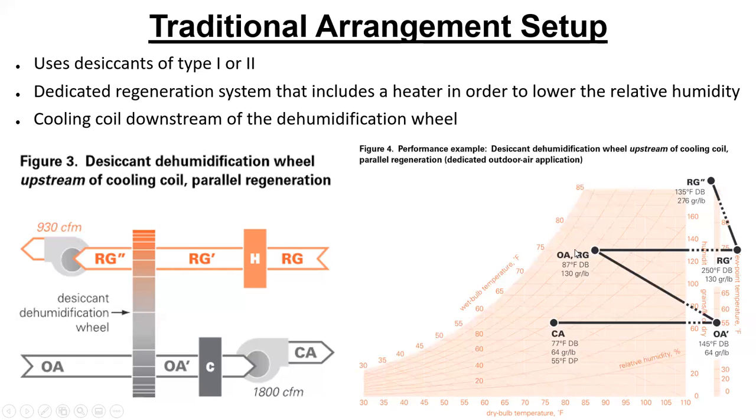All right, and then on the process air side, we've got our outside air that comes in, and it's going straight across that desiccant wheel. Well, that desiccant wheel's hot, right? You just blew 250-degree air across it. And the other part is there's also heat generated when these water vapor molecules are floating around in the air. They have some velocity energy and vibrational energy inside the molecule. It's an H2O, and those little O's are flopping around on bonds.